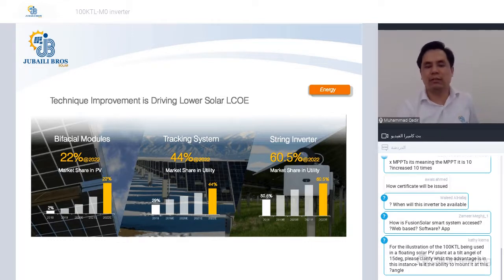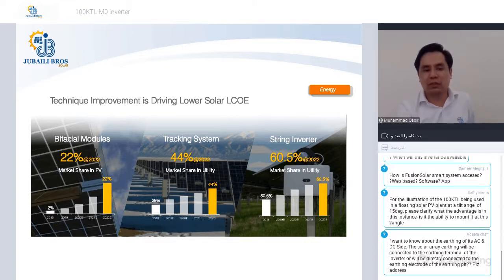As you know, bifacial has been used in many large-scale projects, and it is becoming a new trend. By 2022, Huawei is expecting that 22% of the market share will be occupied by bifacial solar PV modules. Tracking systems will also occupy 44% in the utility scale scenario, and the string inverter market will be more fashionable, occupying 60.5% of market share in the utility scale scenario. So Huawei inverters already have features to accommodate bifacial modules and trackers, and these are already string level inverters, which reduces the failure rate and also increases availability as compared to central inverters or single MPPT inverters.